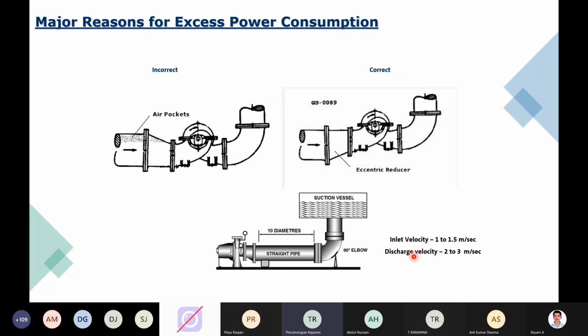Okay. And in terms of your velocity guidelines, because when you talk about the hydraulics of the pipes on the suction and discharge side, obviously the recommended velocity has to be maintained so that the required pressure is met. There are sewage pumps or dewatering pumps, which need a minimum self-cleaning velocity, so that at any point of time the sludge or whatever particles don't settle in your pipes. So certain details like velocity play a very important role in designing your head required at your site based on the layout.